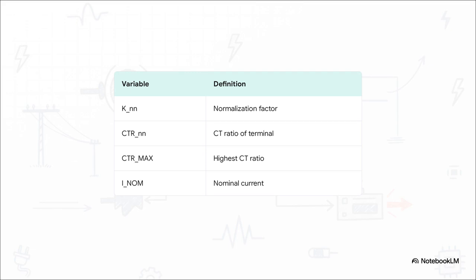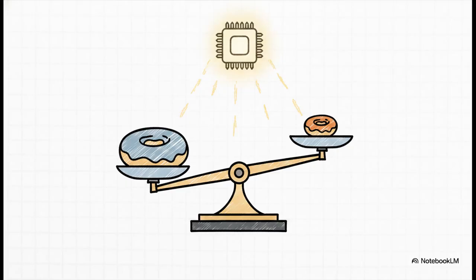Well, the relay uses this KNN normalization formula. It looks at the CT ratio of the specific terminal you're dealing with, compares it against the highest CT ratio used in the zone, and factors in the nominal secondary current. This right here is the true power of numerical relays in action. By applying that KNN factor, the relay converts all incoming currents into per-unit values. It mathematically forces an apples-to-apples comparison.